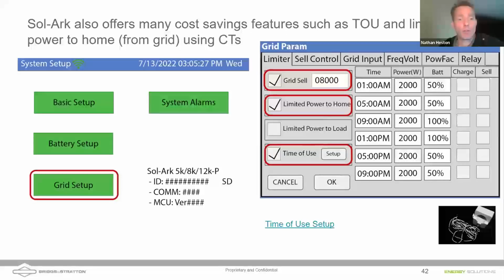On the grid parameters, when you're setting up the grid parameters of the Sol-Ark 15k, you've got a lot of options, and a popular option for setup is what I've enabled on the right. There are different tick boxes that you see there for the grid setup that allow you to do different things. So for instance, with time of use, you can tell the inverter how much power you want to discharge. You can limit how much you discharge at different times of the day. So if you want to use the majority of your battery power when grid power is expensive, you can save some of that power and set that output limit for different times of the day, which you set up on the right side of the screen there.